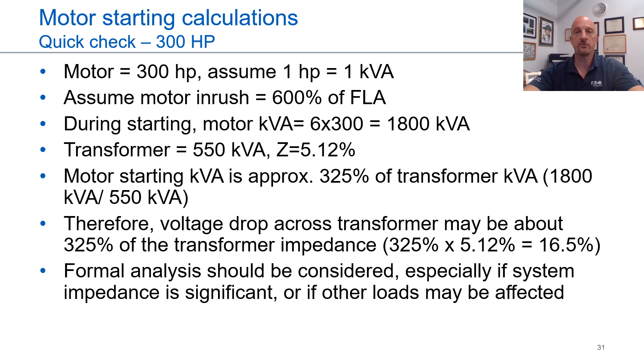Now, one of the questions I get quite a bit of is, you get these peaks and rushes of different things throughout the day. Is motor starting going to affect my demand charge? No, it's really more about understanding what demand charge is. Demand charge is the 15-minute window that the utilities look at to see what your maximum demand is for the month in terms of kilowatts or megawatts.